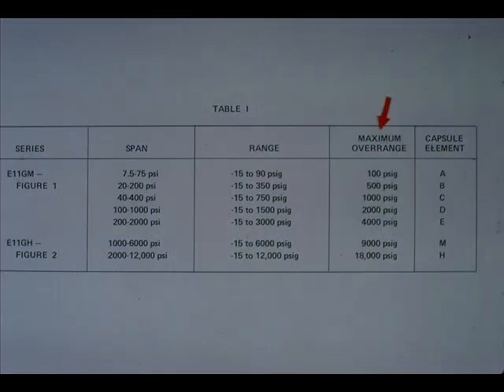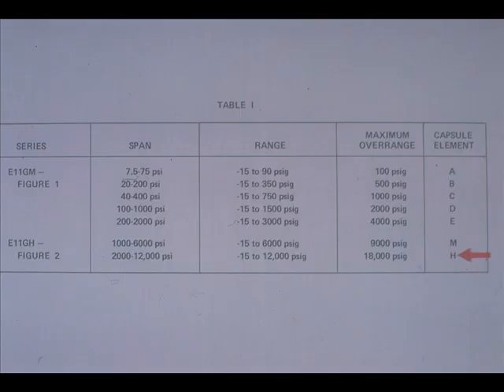Overrange protection has to be considered when making the capsule selection. Two elements, M and H, for the E11GH are listed. These elements are the C-type Bourdon tube and are interchangeable.